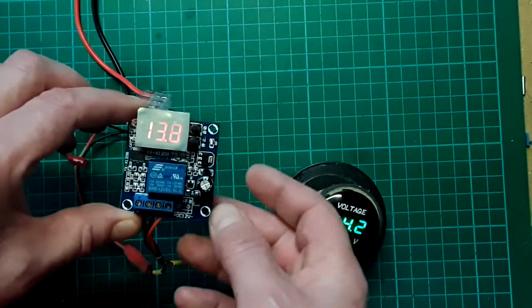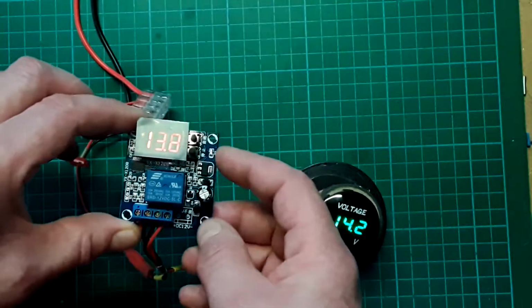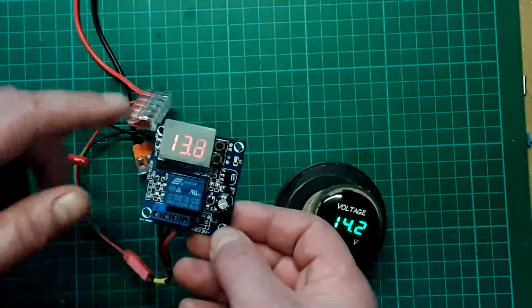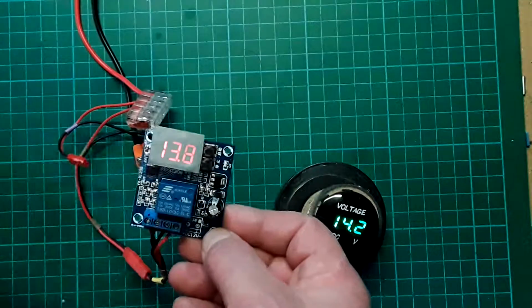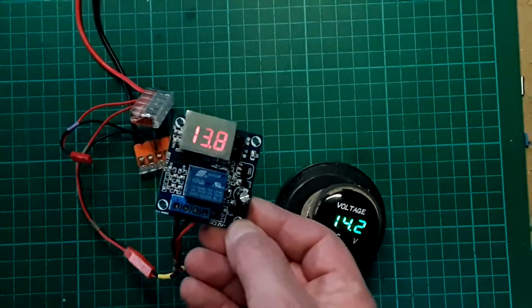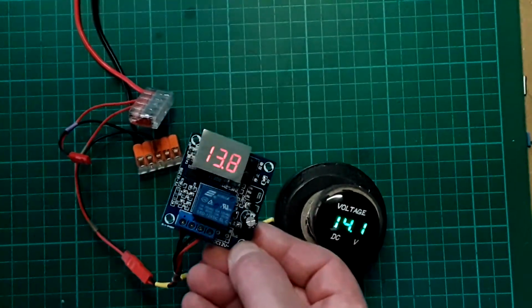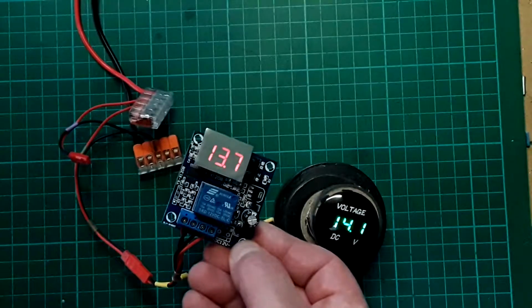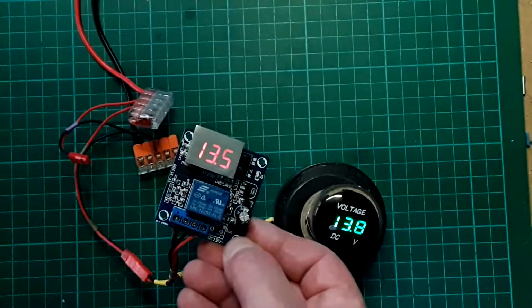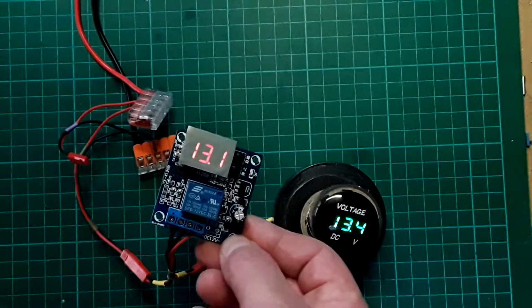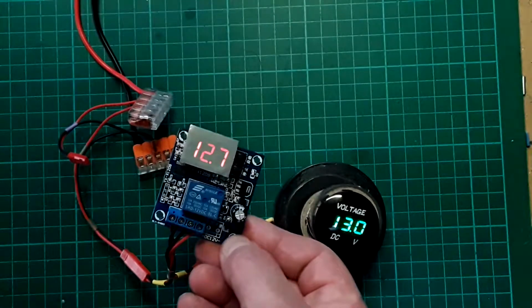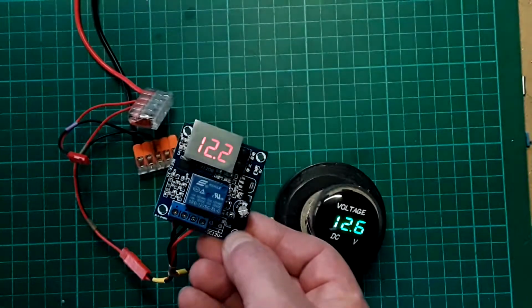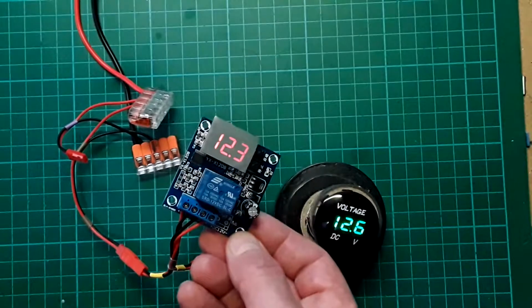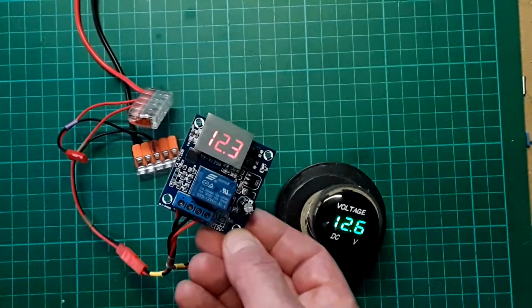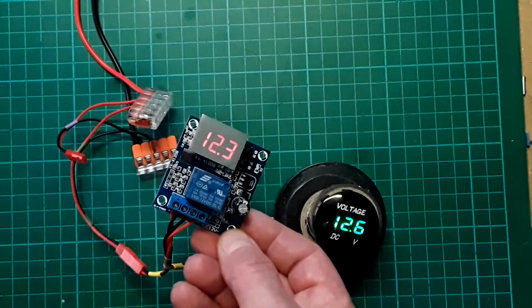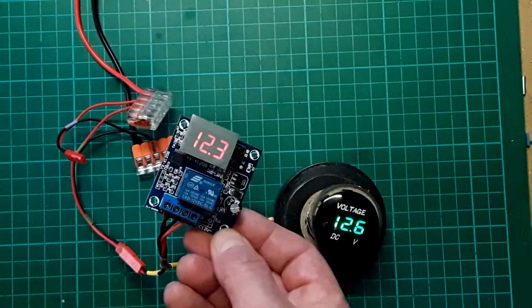There's a little LED on here, and that indicates an error state - in other words, when the relay is de-energized. So if we're at an ideal voltage here and we drop the voltage down, we're going to see it drop out at 12.5, but it doesn't drop out straight away - you have to wait a second or two because it's got a time delay built in there. Again, this is to stop it cycling.